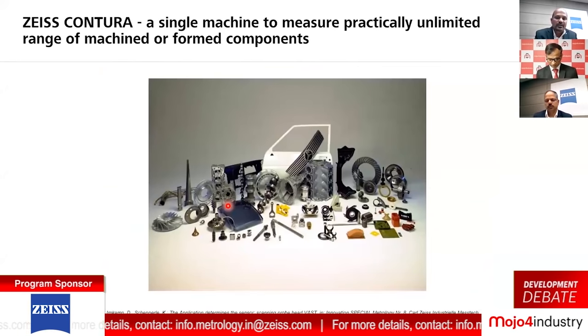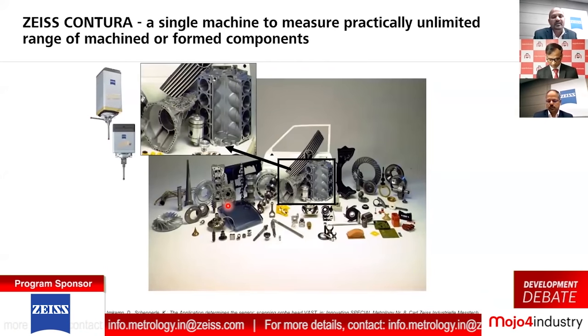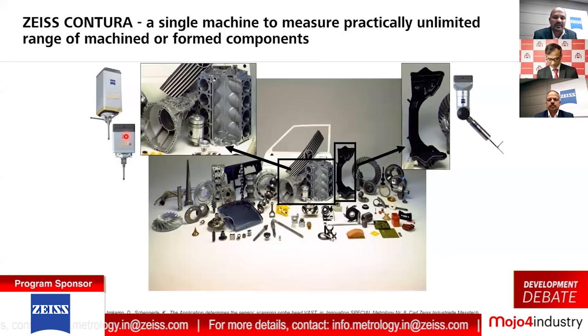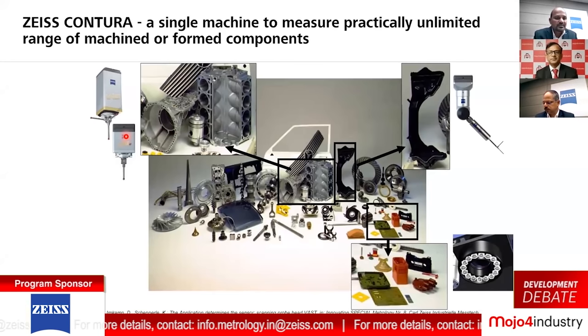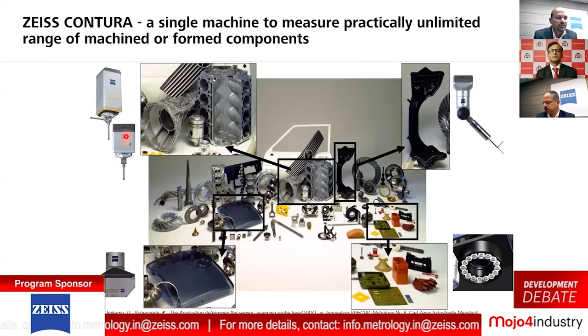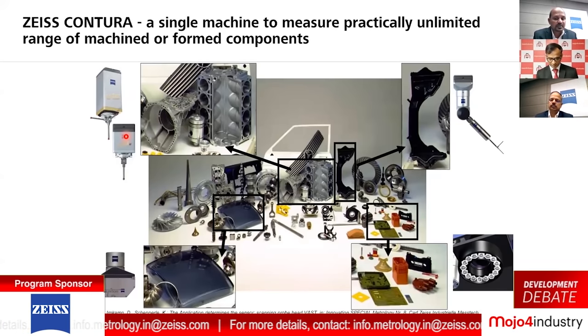Then naturally you would need different kinds of sensors on the CMM. For example, if you're measuring a large engine component or engine housing, you need a sensor or probe head on the CMM that can reach deep interior features - your machine should have those features. For certain fabrication parts or intricate parts with angled holes, you need an articulating probe head. If there are plastic parts, you should have non-contact measurement capability on your CMM. Similarly, for freeform surfaces, say for quick reverse engineering, you should have a non-contact laser sensor that can be fixed on your machine. So can all these interfaces and probe heads be fixed on the ZEISS Contura? The answer is yes.